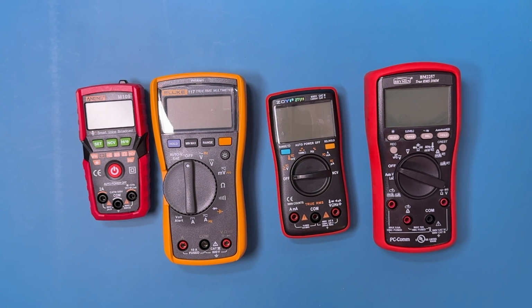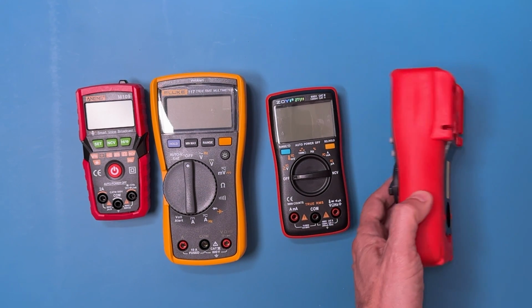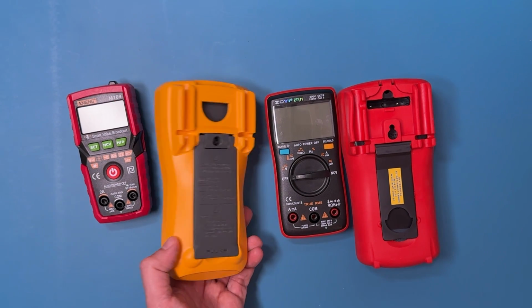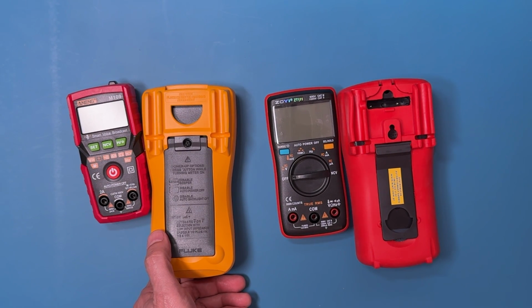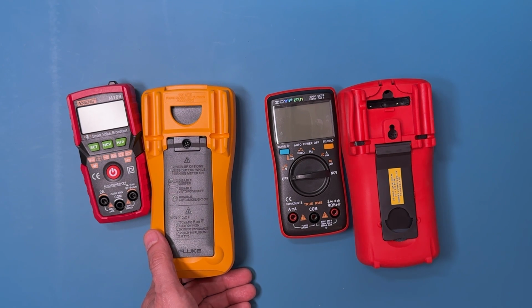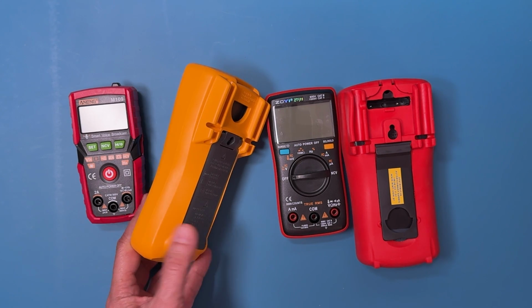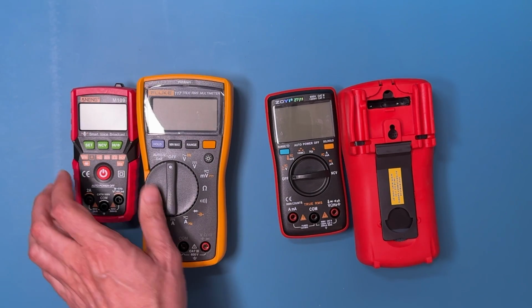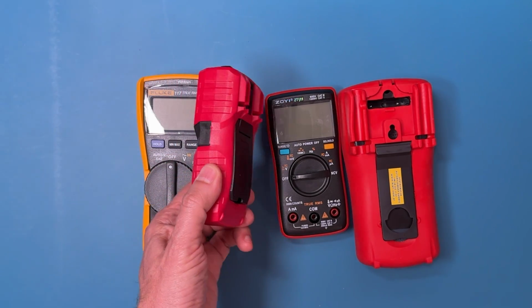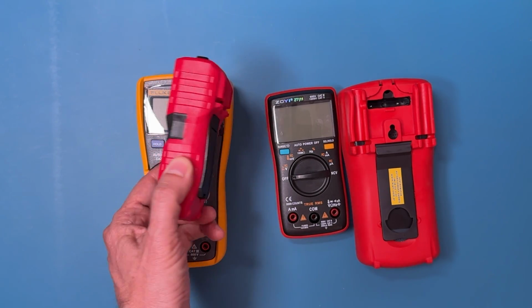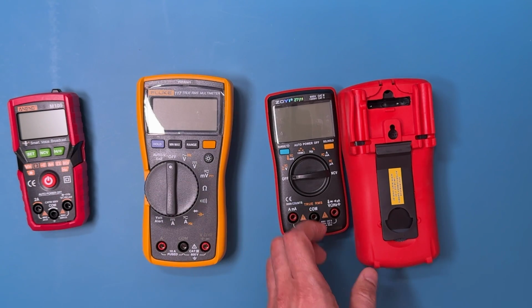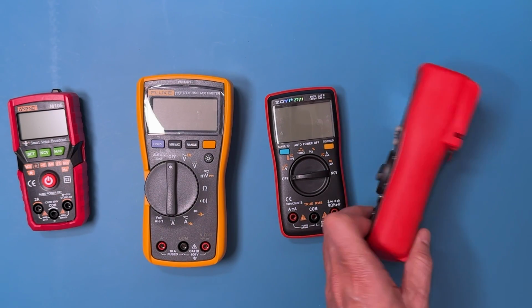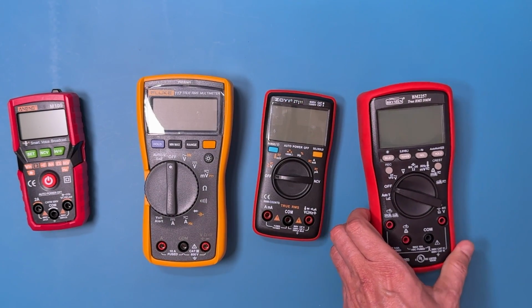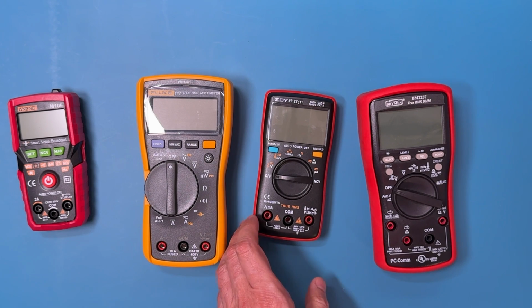reliably. This is why most handheld meters have large rubber overmolds. These are meant to protect the unit and absorb the shock from drops. At the high end, the overmolds are like protective cocoons. At the low end, these are more decorative than protective. There's a definite price premium for meters that can withstand being frequently knocked about while continuing to operate both reliably and safely.